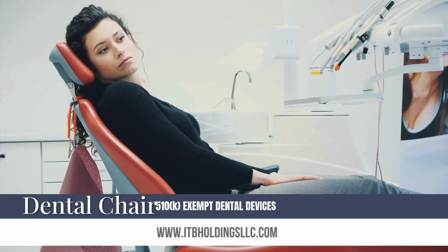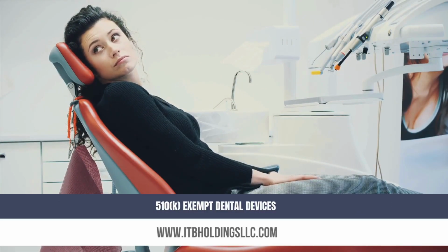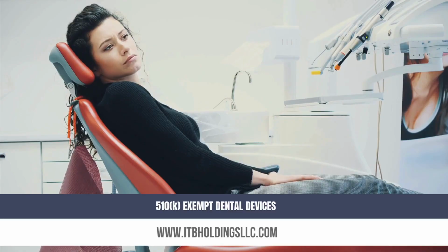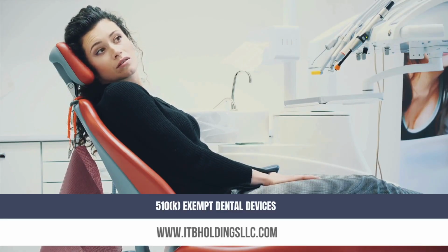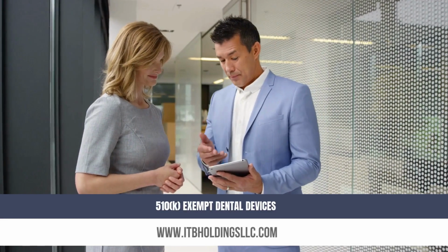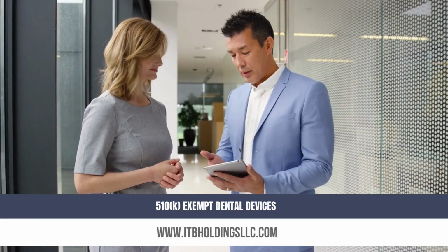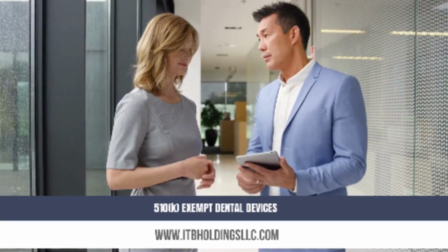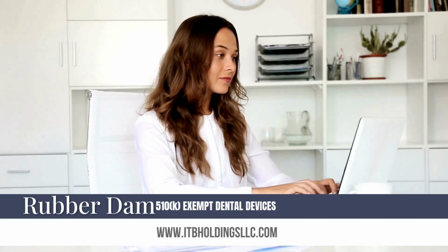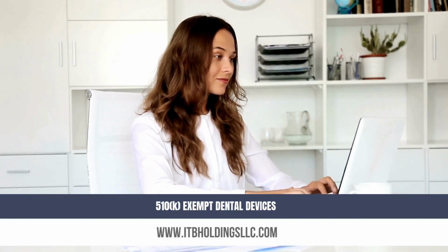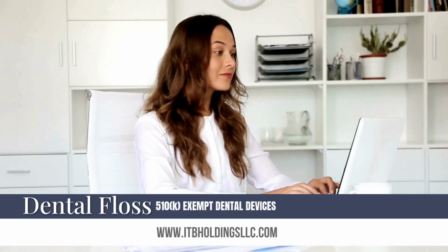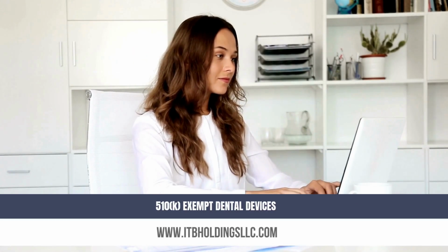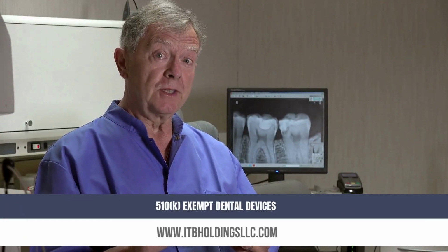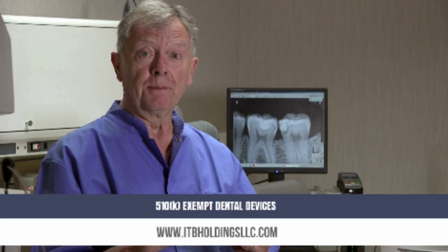Let's talk about dental chairs and their accessories. Only chairs without an operative unit device are 510(k) exempt. A dental chair with an operative unit, product code KLC, requires 510(k) clearance. However, a dental chair without an operative unit, product code NRU, is exempt from 510(k). Now moving on to rubber dams and their accessories, only the accessories are 510(k) exempt. Dental floss is 510(k) exempt only if the device is made of inert materials and is not coated or impregnated with chemicals intended to provide a therapeutic benefit or interact with tissues of the oral cavity.